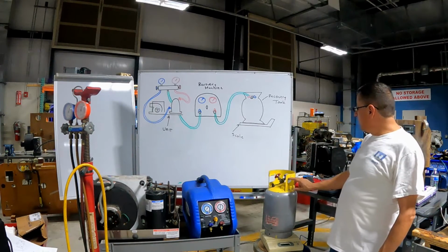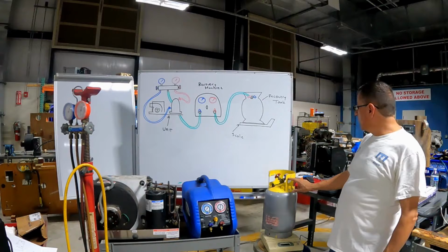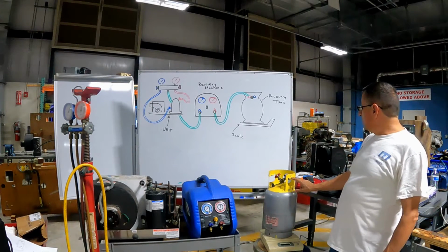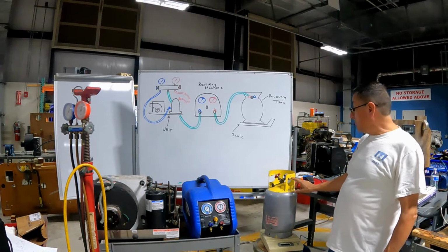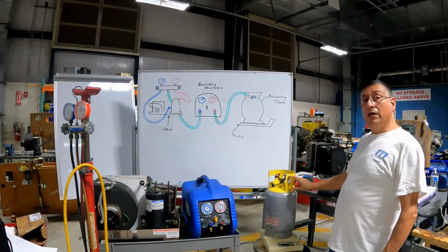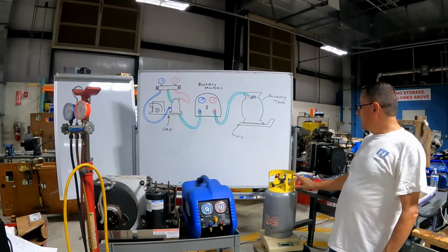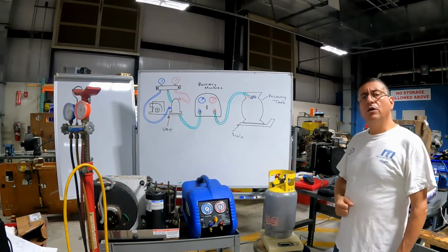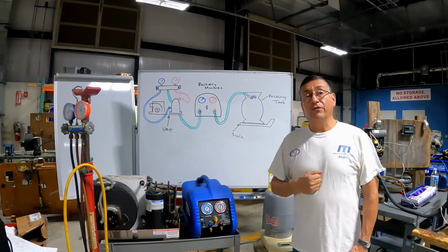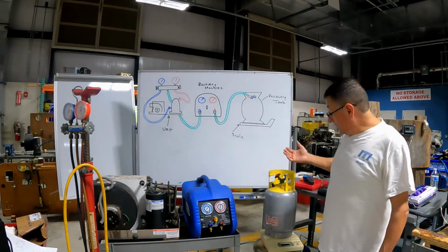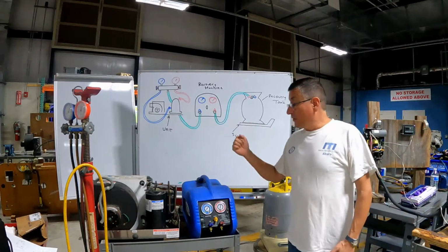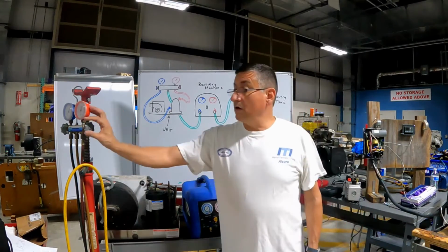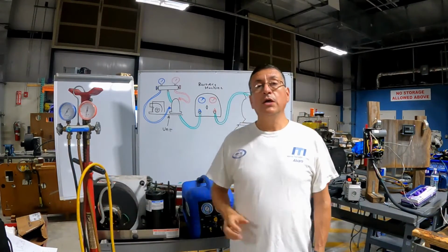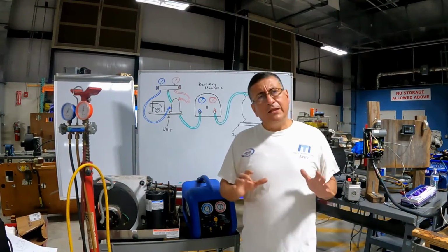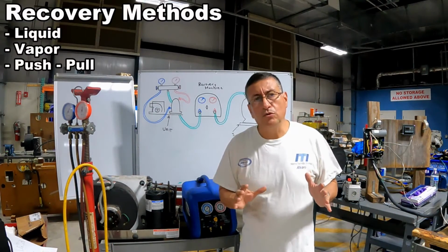Normally the cylinder has a label with the weight: empty, 18 pounds, and with the refrigerant, 26. In other words, with this cylinder you can recover 8 pounds of refrigerant. Okay, we have the cylinder, we have the scale, we have the recovery machine, we have the set of gauges, the additional hose. Now we are going to talk about the different types of recovery methods.